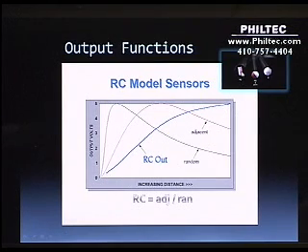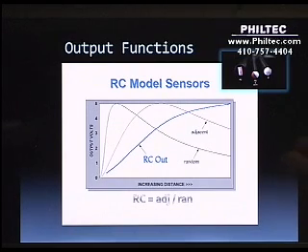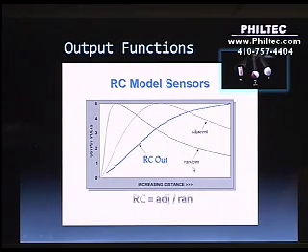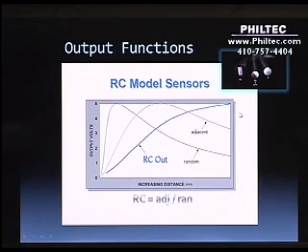The adjacent bundle — the red area in these pictures — generates a curve which is shown by the red line here. This is basically similar to another D model, but its optical peak falls at a much larger distance than the random mix bundle. In the electronics, we ratiometrically process the output of the random and the adjacent bundles. That ratiometric measure is shown here with this RC output function, which is a single-valued function and is insensitive to reflectance variations of the target surface.